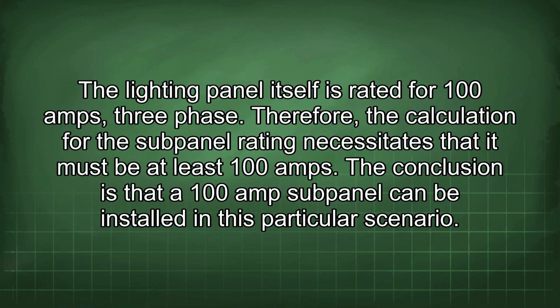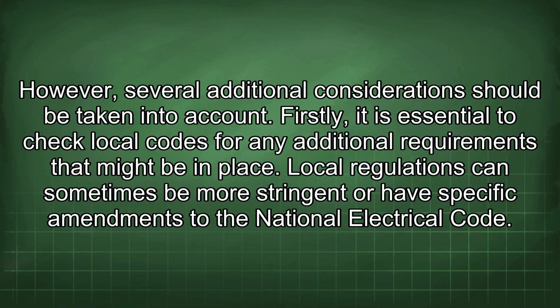The lighting panel itself is rated for 100 amps, 3-phase. Therefore, the calculation for the subpanel rating necessitates that it must be at least 100 amps. The conclusion is that a 100 amp subpanel can be installed in this particular scenario. However, several additional considerations should be taken into account.